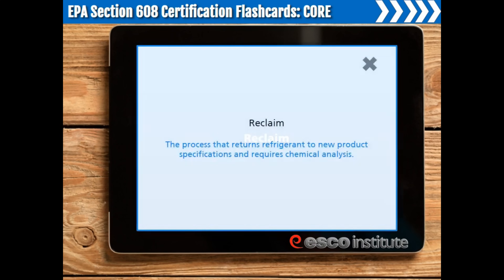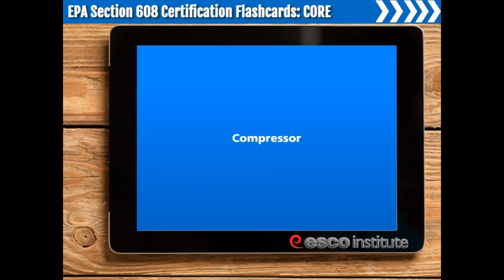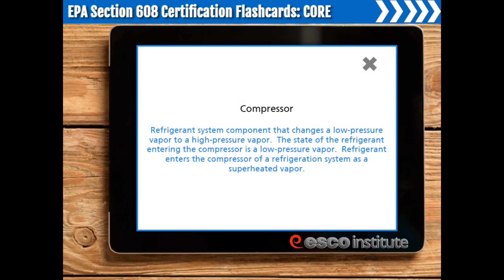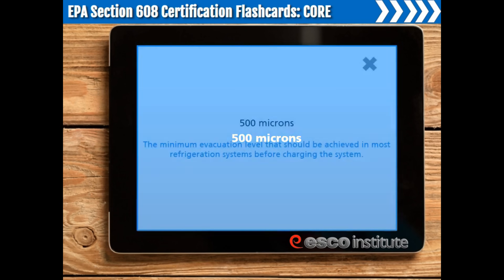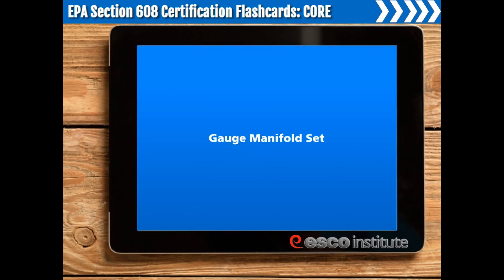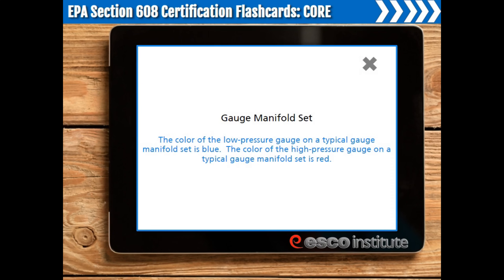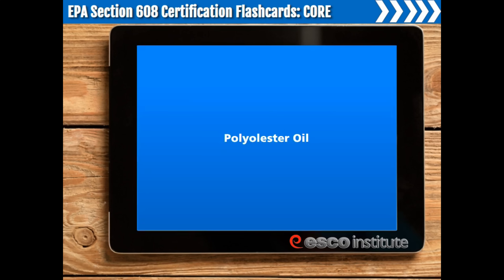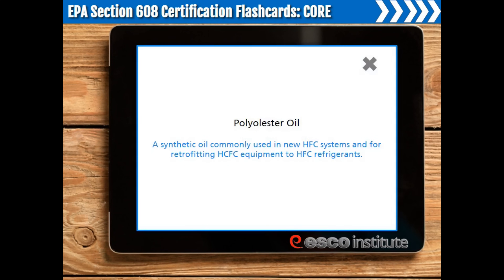Reclaim. Reclaiming is the process that returns refrigerant to new product specifications and requires chemical analysis. Compressor. A compressor is a refrigerant system component that changes a low-pressure vapor to a high-pressure vapor. The state of the refrigerant entering the compressor is a low-pressure vapor, specifically a superheated vapor. 500 microns is the minimum evacuation level that should be achieved in most refrigeration systems before charging. The low-pressure gauge on a gauge manifold set is blue; the high-pressure gauge is red. Polyolester Oil is a synthetic oil commonly used in new HFC systems and for retrofitting HCFC equipment to HFC refrigerants.